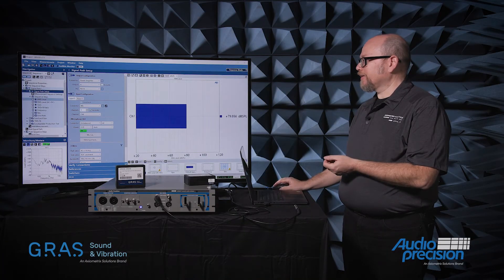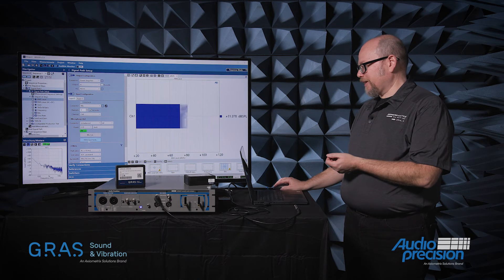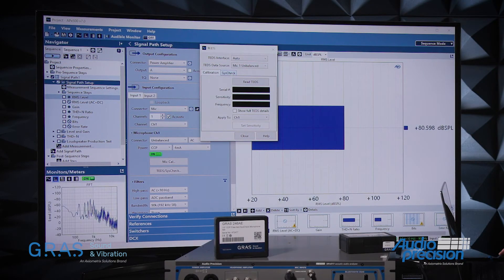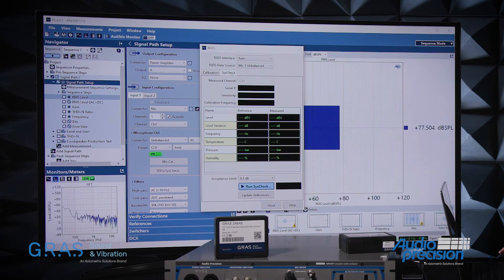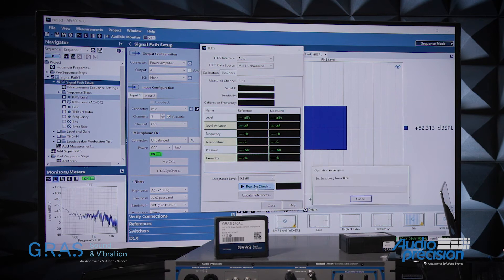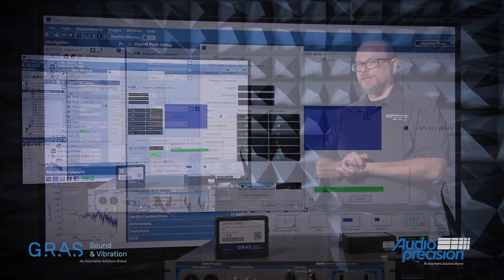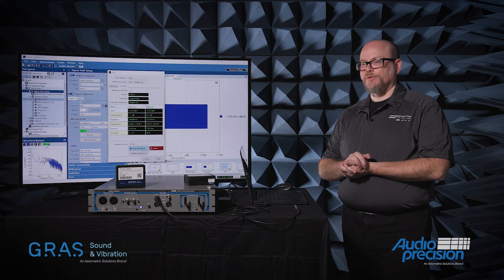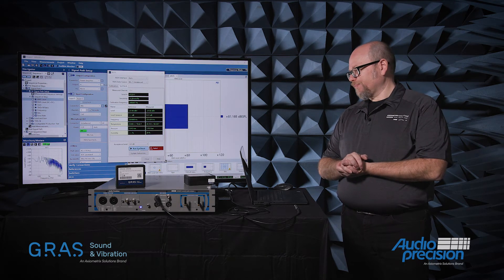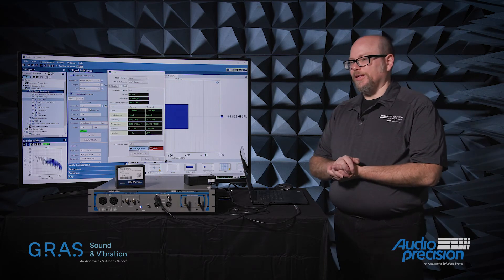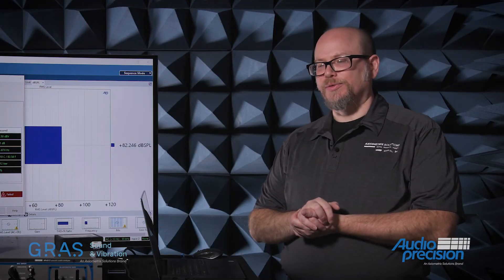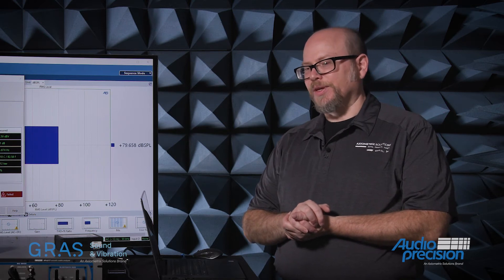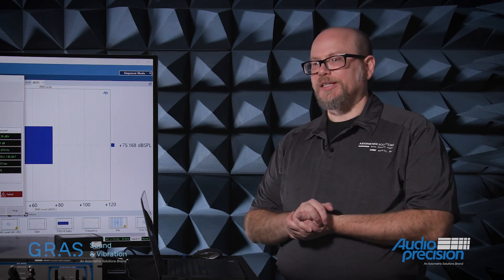If I go in the APX500 software, again into my TEDS SysCheck dialog, this time I'll select the SysCheck tab and select Run SysCheck. Unlike just reading TEDS data, this is an active process. There is actually a signal generator embedded in the preamplifier body of the microphone. That signal generator is in parallel with the output of the capacitor, or the diaphragm, of the microphone, and we actually sense any deviation in sensitivity.